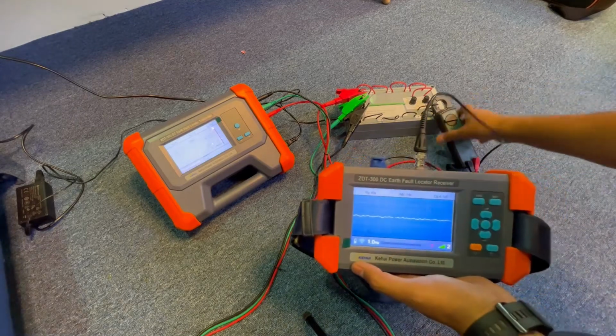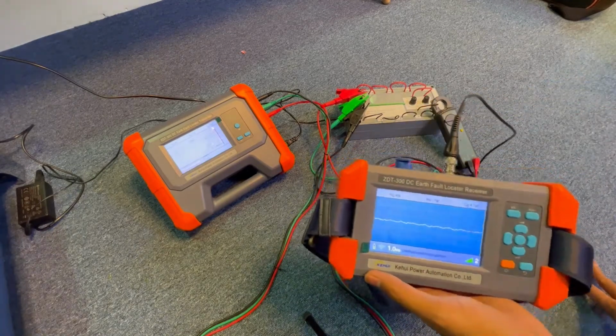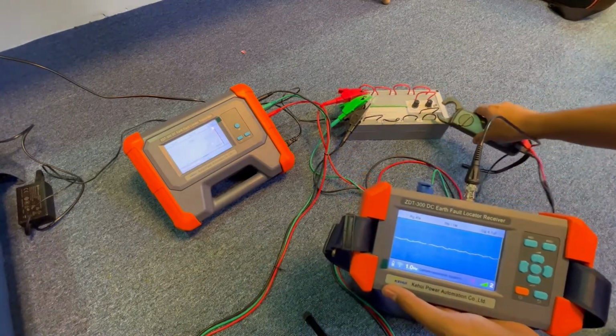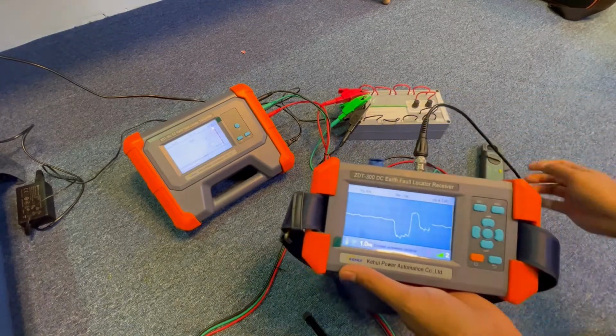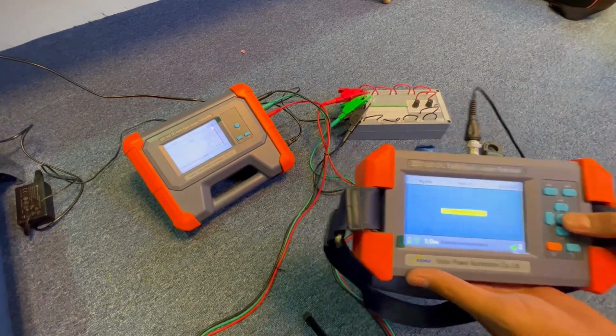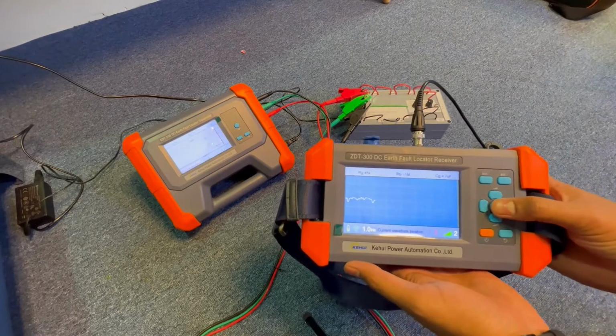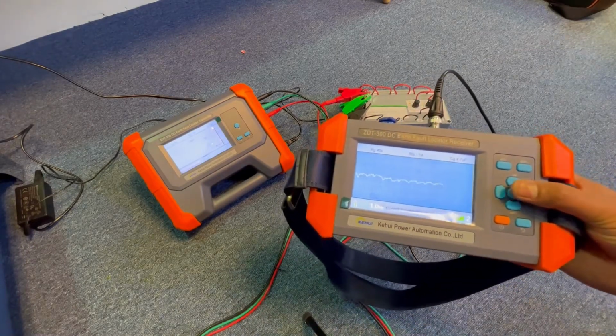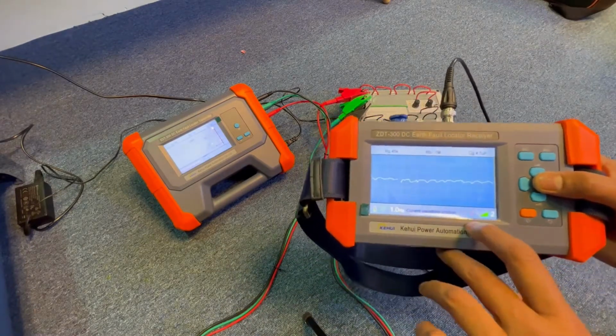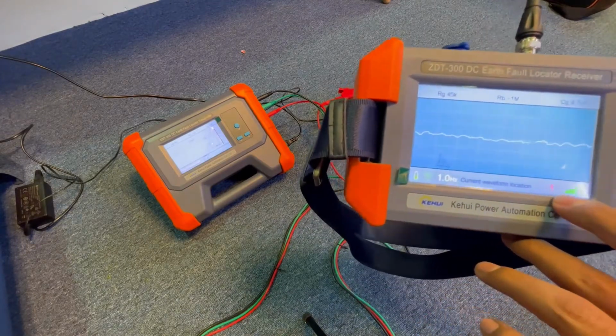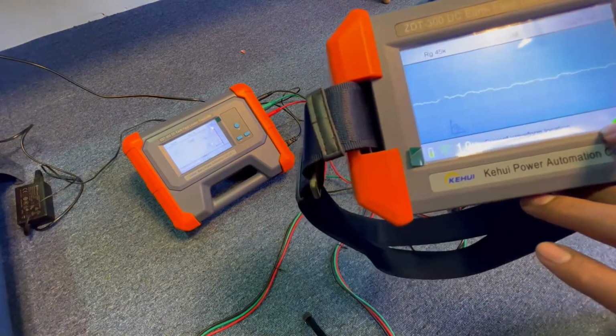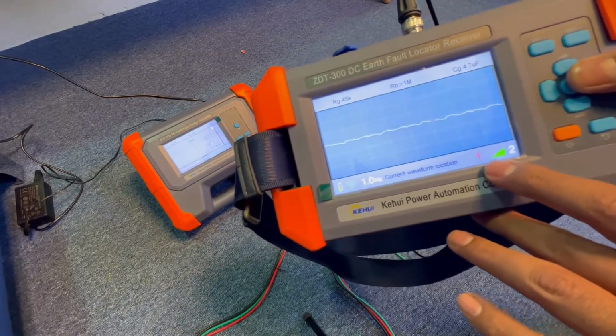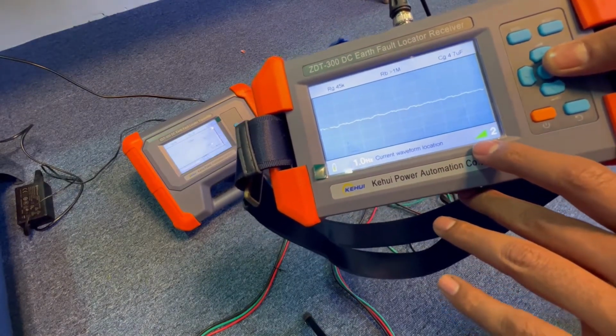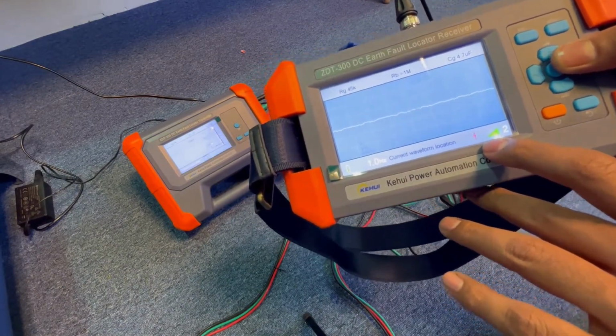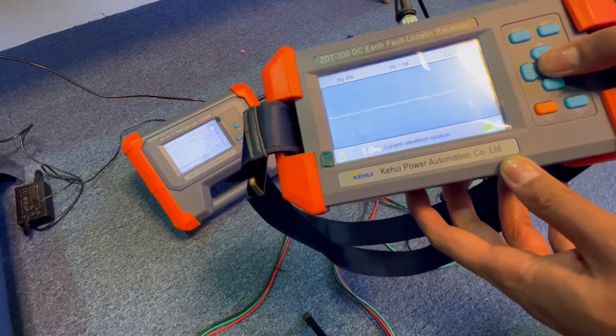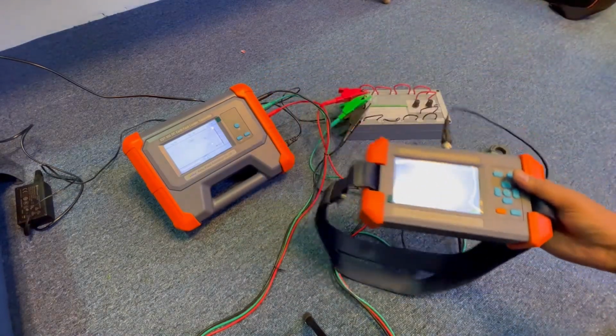So let's see how our big sensor can help you. You have seen the sensor here. So always clamp and refresh so that you can see the signal, and then you press this center button once you find out the fault. Once you pinpoint the fault, then this injection will stop. So always check that this transmitter is injecting. If the transmitter is not injecting, then you cannot find the trace of the faulty feeder. So I'll stop the signal now. Let's move with the bigger clamp.